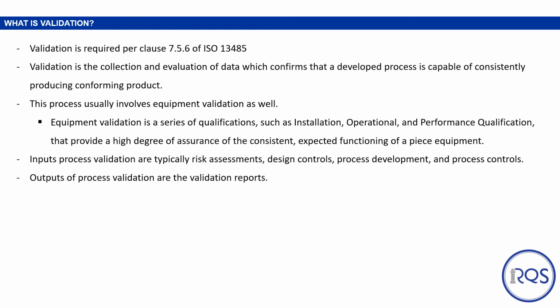Validation is required per clause 7.5.6 of ISO 13485. Validation is the collection and evaluation of data which confirms that a developed process is capable of consistently producing conforming product. This process usually involves equipment validation as well. Equipment validation is a series of qualifications, such as installation, operational, and performance qualifications, that provide a high degree of assurance of the consistent expected functioning of that piece of equipment. Inputs to the process validation are typically risk assessments, design controls, process development, and process controls. Outputs of process validation are the validation reports.